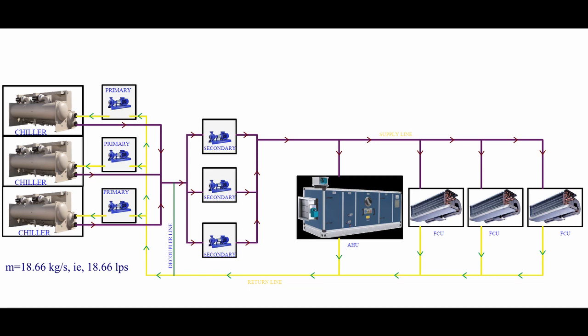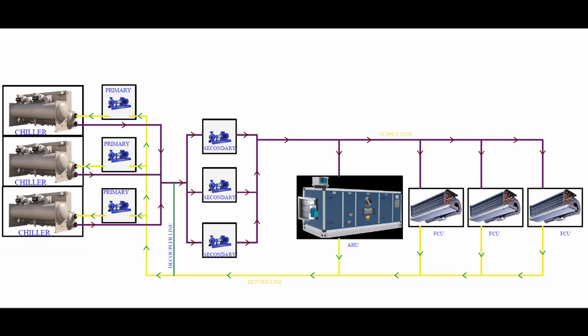Water is the standard fluid, so the volume flow rate and the mass flow rate of water are the same. The volume flow rate of water required is 18.66 liters per second. So it is clear that each chiller is able to extract 200 tons of refrigeration from the building with 18.66 liters per second of volume flow rate. In the same way, all the equipment in this loop will have a coil load, flow rate, and delta T.